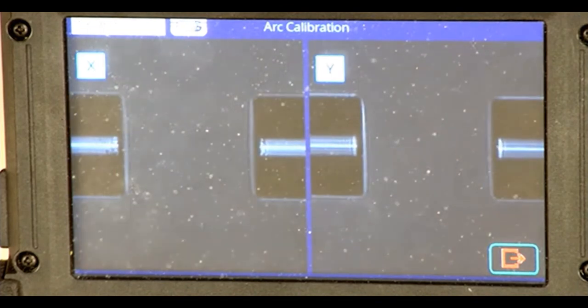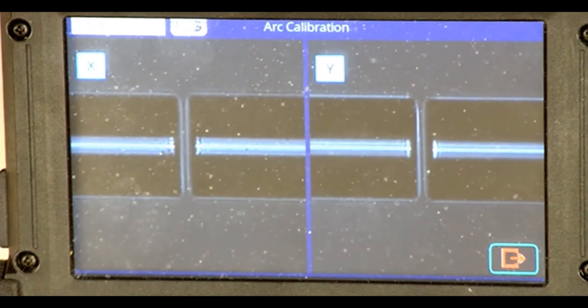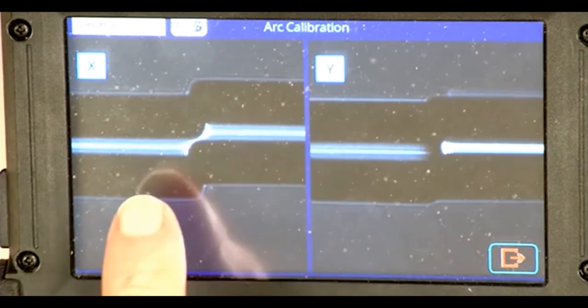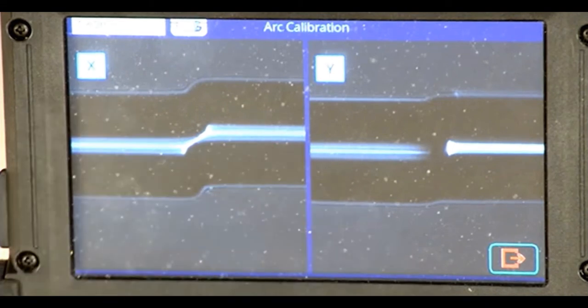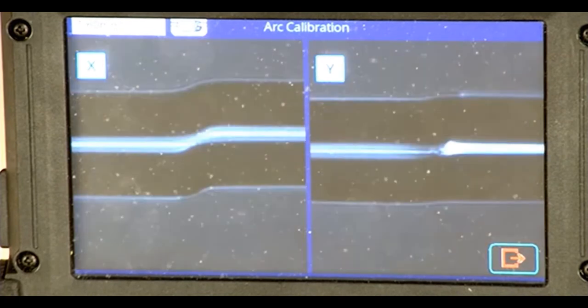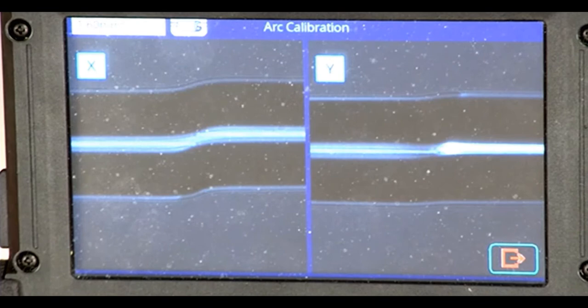Okay, the arc calibration is now starting. So first it arcs several times and you can see it flashing. That was just to find the center brightness of the arc. In other words, it determined the path of the plasma field from one electrode tip to another. Now it's offset the fiber by about 20 microns, splices them together, and it reheats and watches how much it self-centers in the X camera field of view. If it self-centers too quickly, the arc is too hot and it's going to turn the power down. If it self-centers slowly, then it knows the arc is not hot enough, and it will then increase the power. So it does a series of arcs. So this is that manual arc calibration that I told you to do once a day.